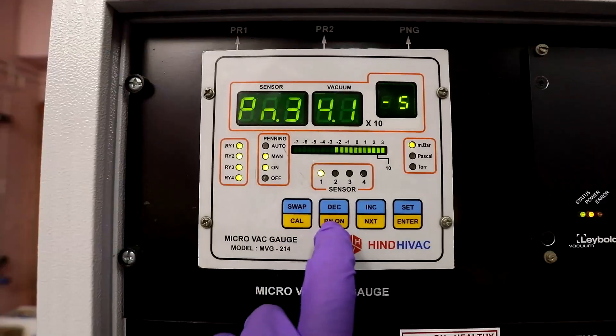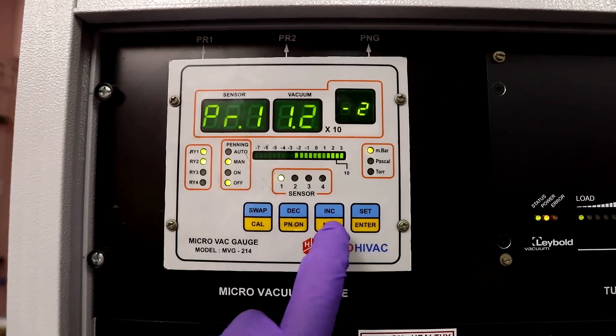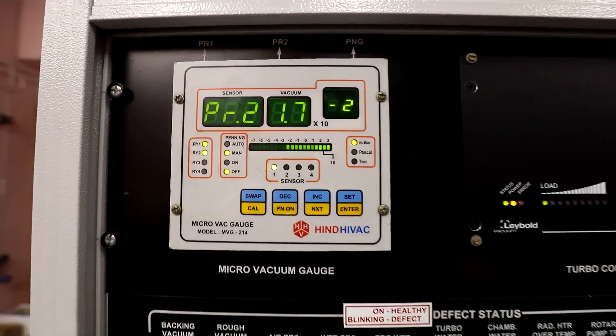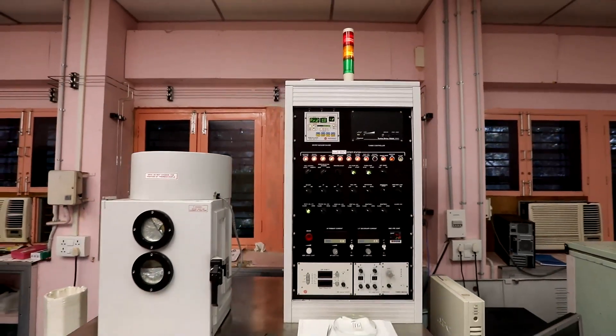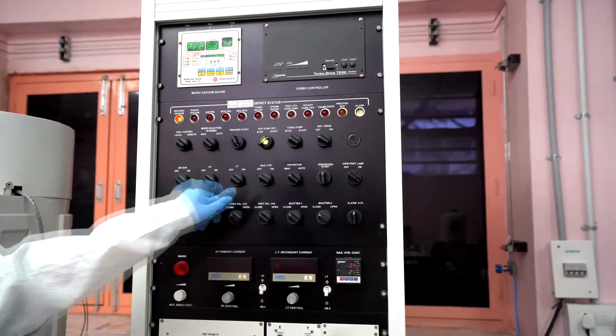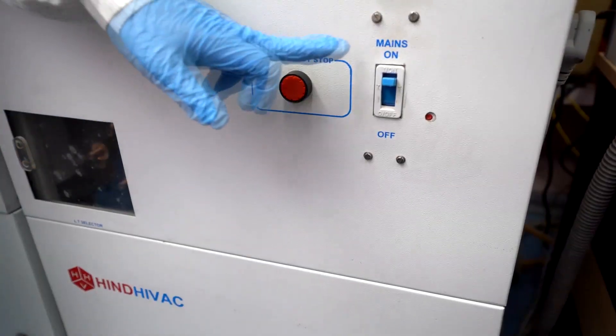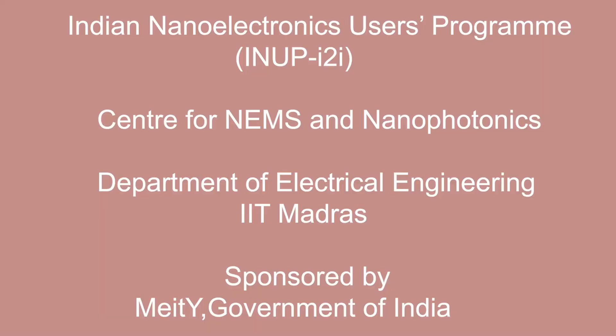At the end, let us close the chamber and create the roughing pressure at 10 to the power of minus 2 millibar inside. Switch off all switches in the reverse order as we did at the start of the process.